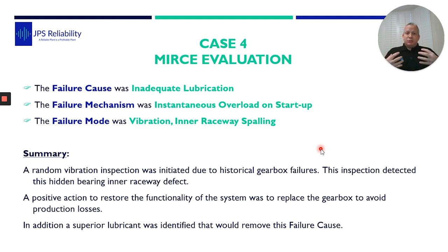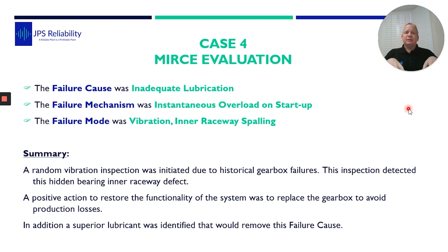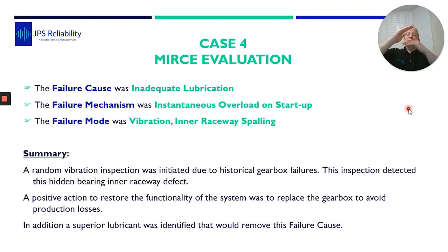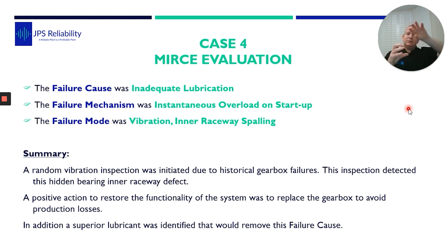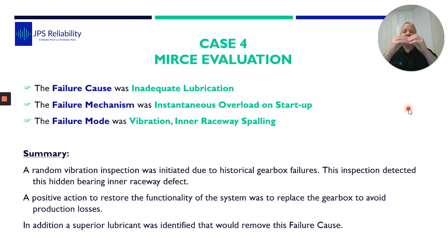When we took a step back, I also had other experience with these gearboxes. What happens is when they shut down for weekends or maintenance, the oil drains to the bottom of the gearbox — which sits at 45 degrees — and settles in a little corner. The gearbox has the right amount of oil and the correct lubricant spec from the OEM. But on a split second at startup, as the weights come around, at that one point of the inner race where the load is highest, there is not enough lubrication. This causes the bearing elements to be squeezed hard, resulting in subsurface fatigue cracking and then spalling.